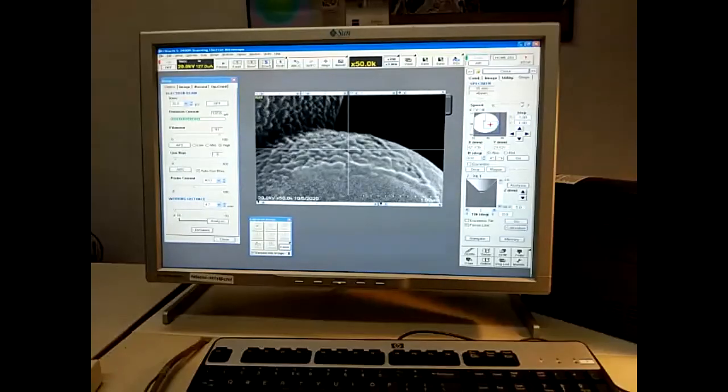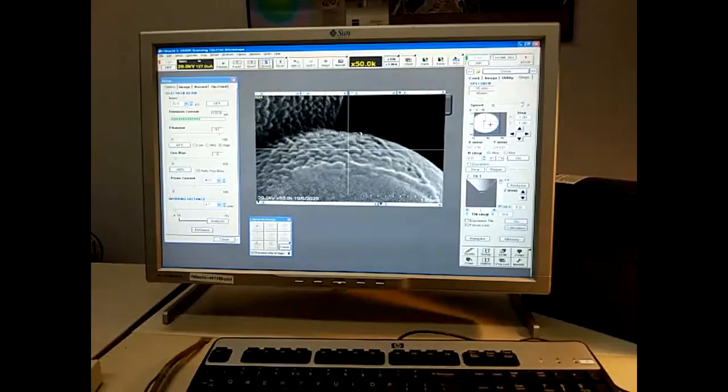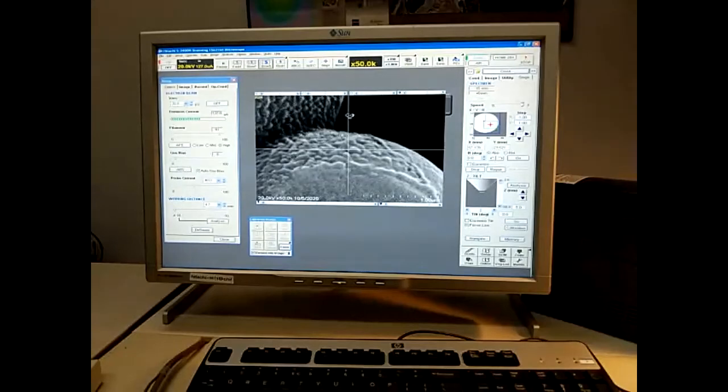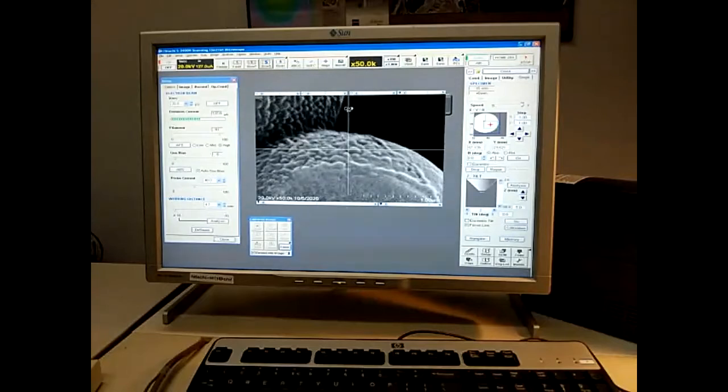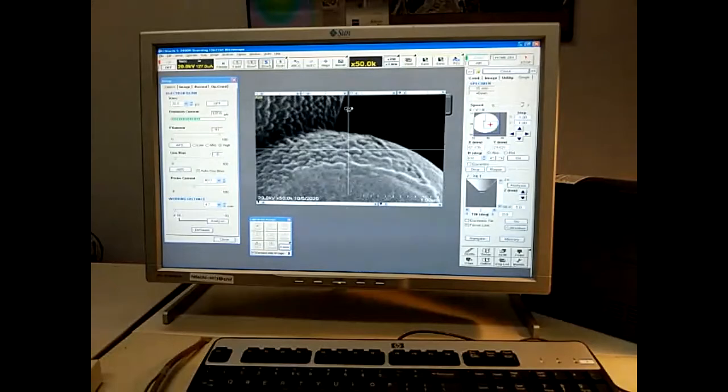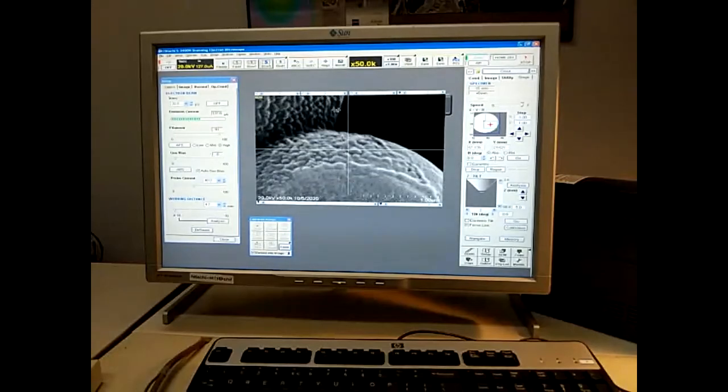Resuming the recording. This is approximately 50,000x at 20 kV. This sample is not heavily coated with gold in terms of electron transmission, so it's not the best sample for doing up to 100,000 times. This is about as far as I take this machine normally. You can see that the focus gets a little softer in this range, but it still is capable of going higher.